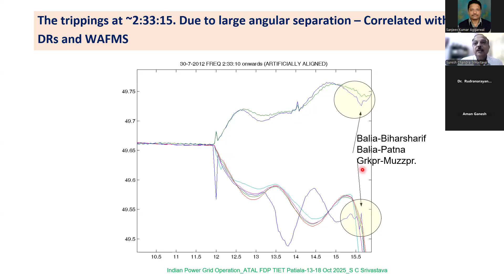Now, this is the point of separation, I think. So no startup power was there. That is why it took a lot of time. This is the 31st. What happened? They did not understand why it had taken place. They thought that there was a momentary fault and the line was reconnected. At that time they found overvoltage in a certain part of the eastern line, so some of the lines were taken out.